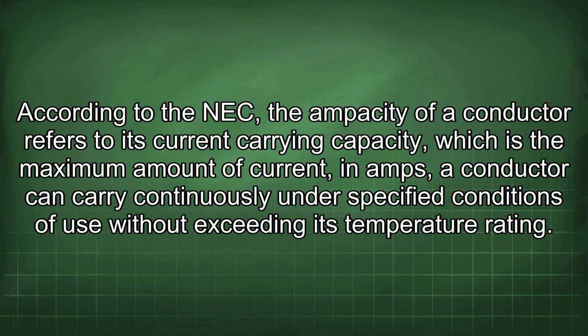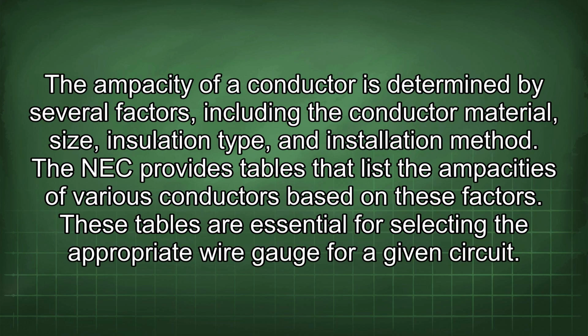According to the NEC, the ampacity of a conductor refers to its current carrying capacity, which is the maximum amount of current in amps a conductor can carry continuously under specified conditions of use without exceeding its temperature rating. The ampacity of a conductor is determined by several factors, including the conductor material, size, insulation type, and installation method. The NEC provides tables that list the ampacities of various conductors based on these factors. These tables are essential for selecting the appropriate wire gauge for a given circuit.